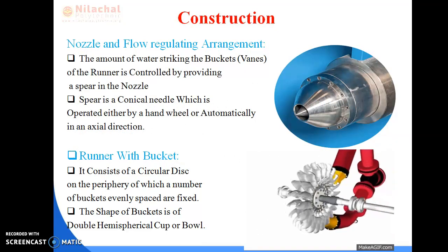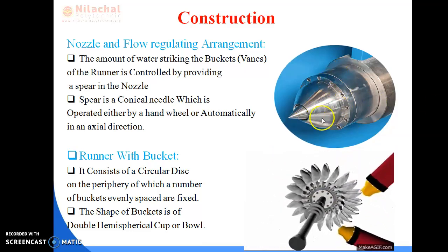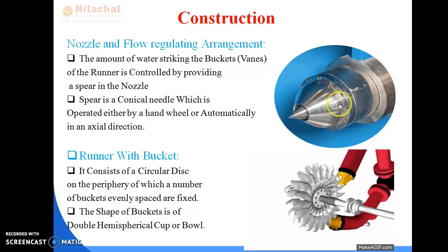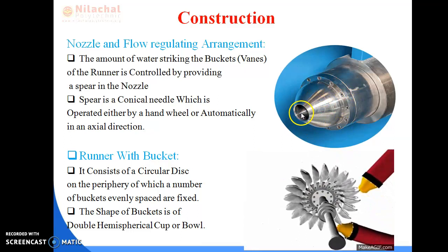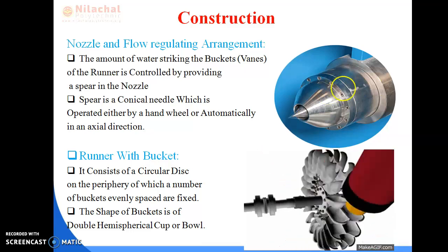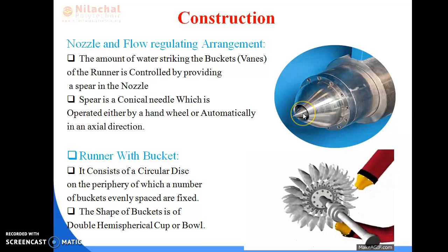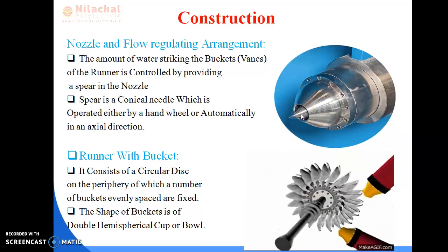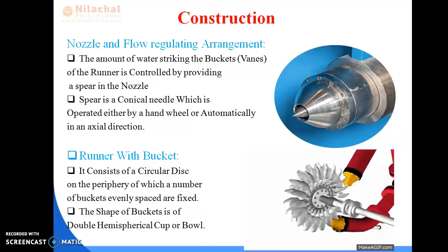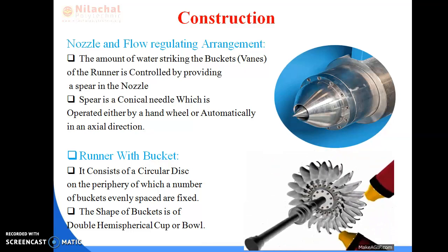First, we need to understand the use of the nozzle and flow regulating arrangement. As shown in the figure, we have a pipe — the penstock — whose end is attached to the nozzle. Inside the nozzle, there is a conical part, a conical needle, which moves inside the passage of the nozzle. The movement of the spear inside the nozzle controls the mass of liquid flowing through the nozzle according to the requirement at the turbine unit.